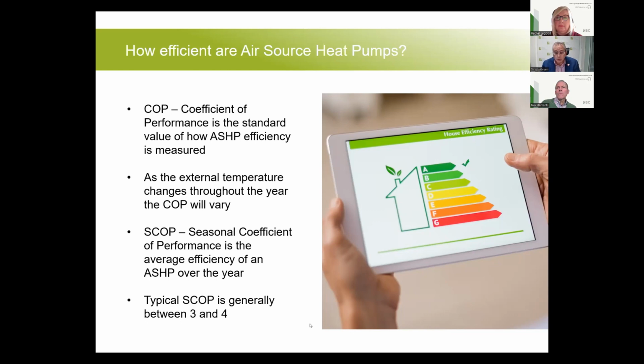But if you are trying to do a like-for-like replacement, and I've got an example on that to come, you may have to work out that the temperature of the radiators needs to be 70 degrees. When it's -5 outside, that can drop the COP at that specific moment down to 2.2, compared to an average where you could be at 4. So at that particular period, it's costing you twice as much to run that heat pump as if you had allowed the higher temperatures. But we'll talk about that in a minute with some more examples. So if we go to the next slide.